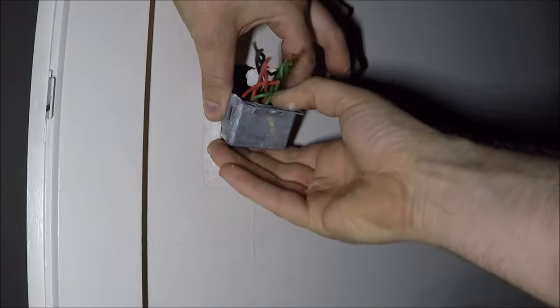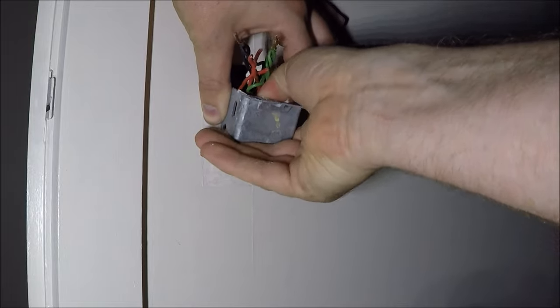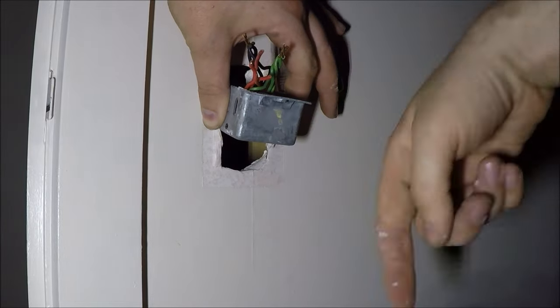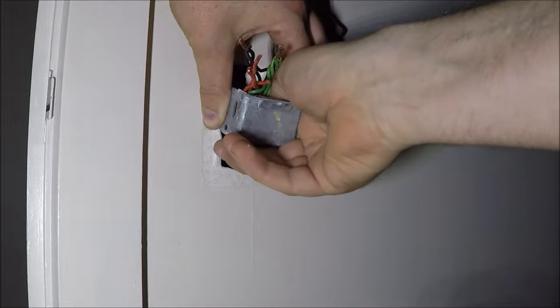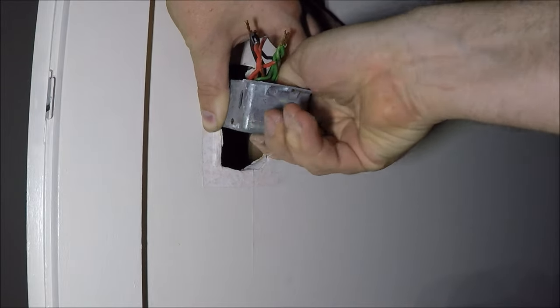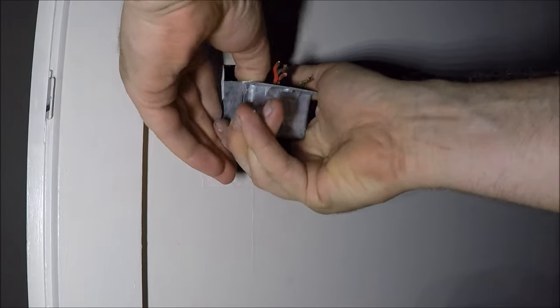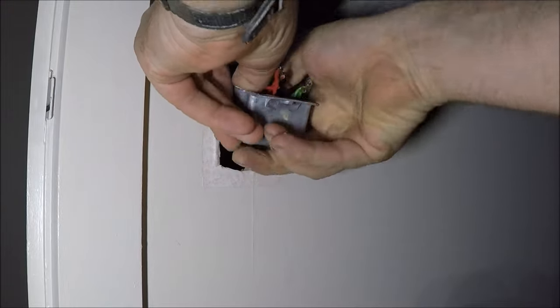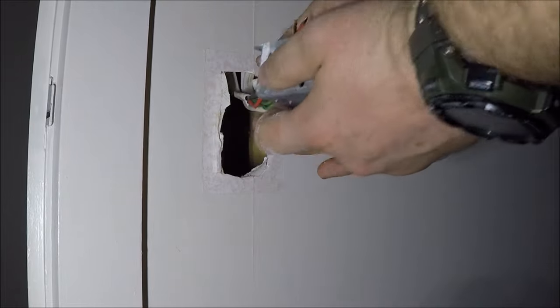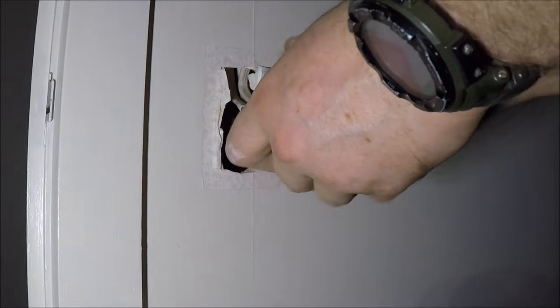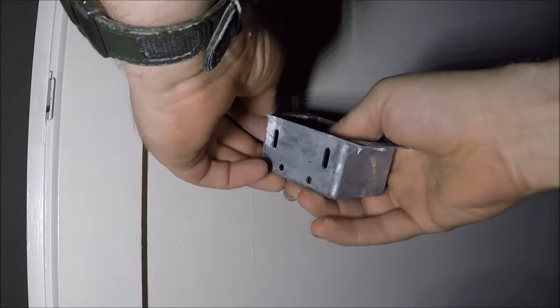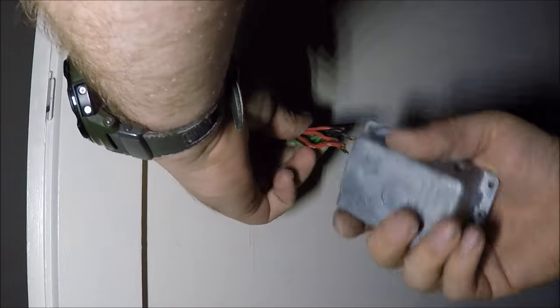Just be careful of the wallpaper as you take them out. You don't have to take them right out, you can just shove them down and push them down the wall on the inside so they're gone for good. And also watch when you take them out that you don't lose cable ends in the walls, because sometimes they're a nightmare to fish back out. And also as you're pulling the box off, make sure it's not nicking the edges of the cables.